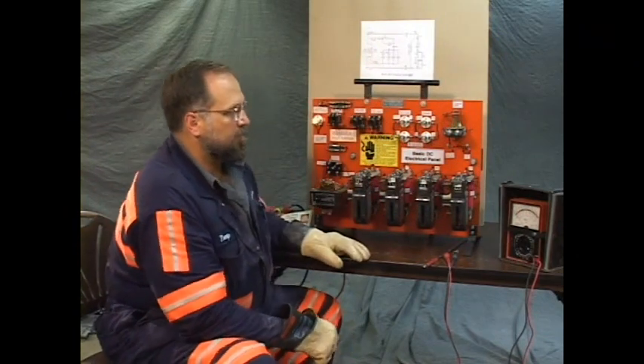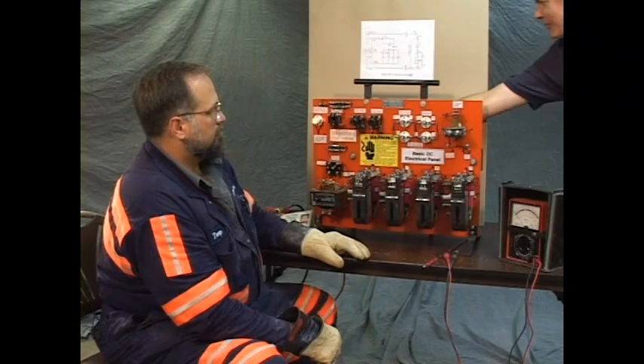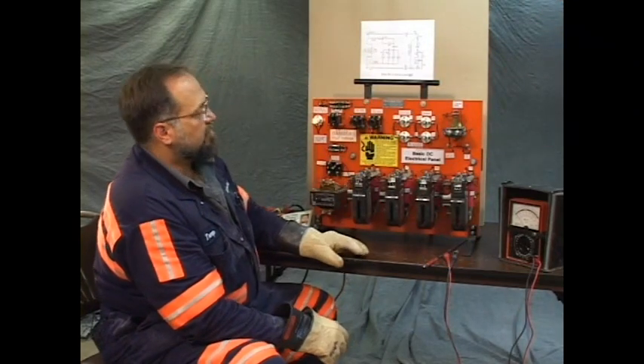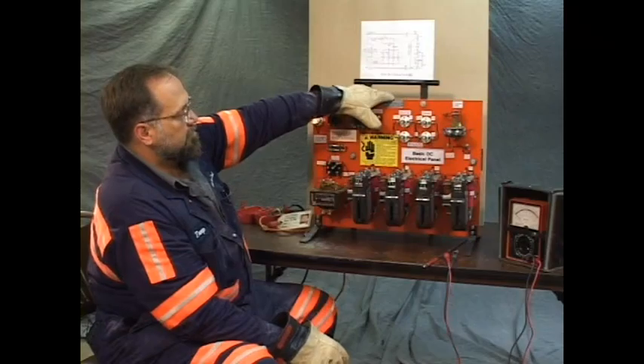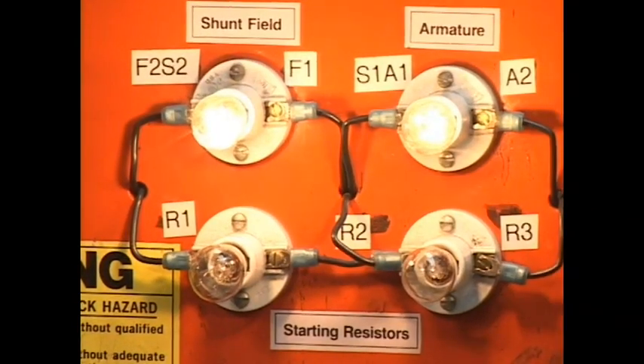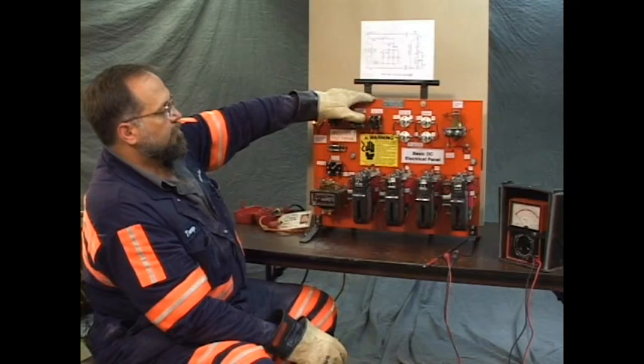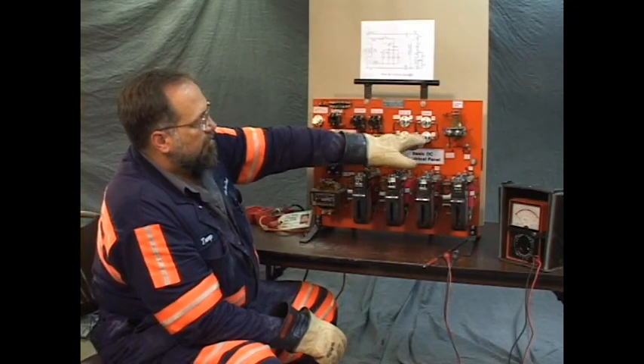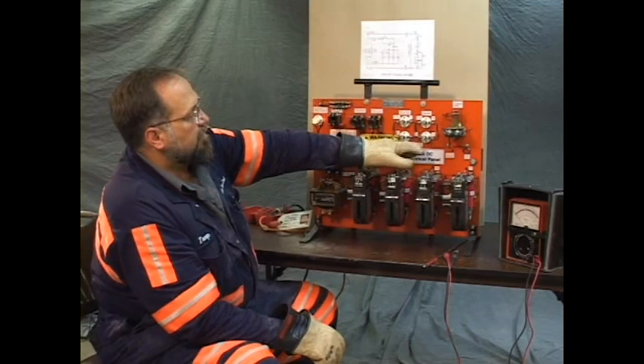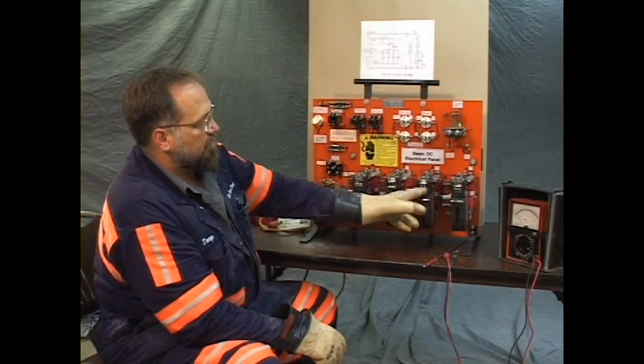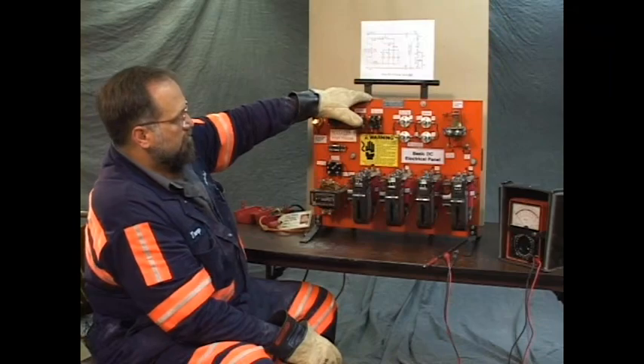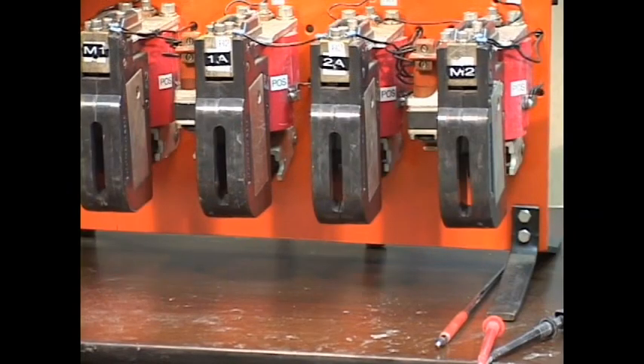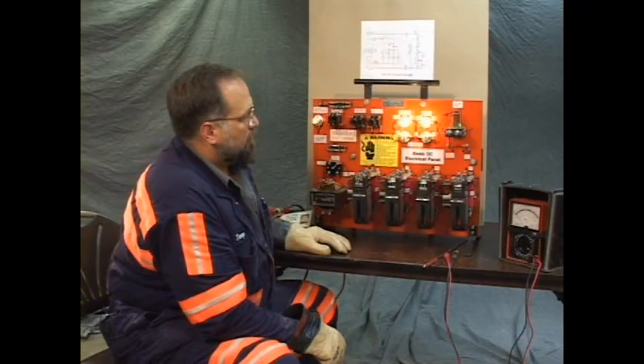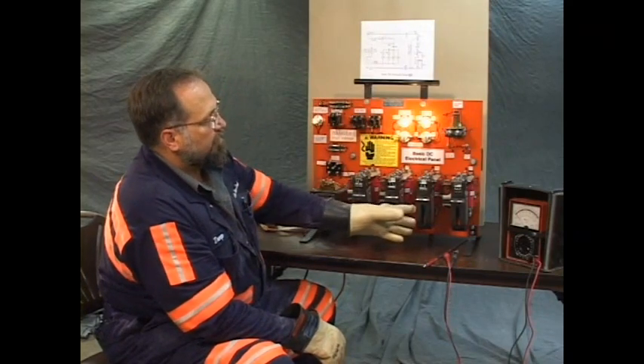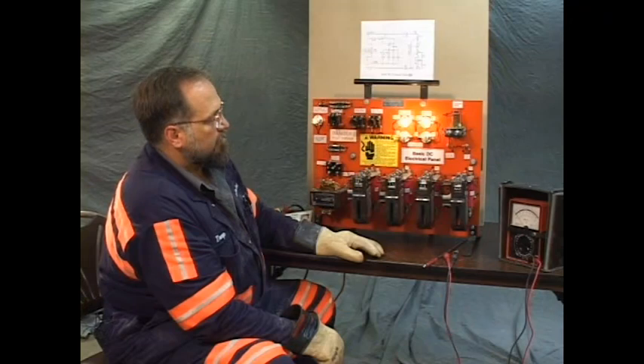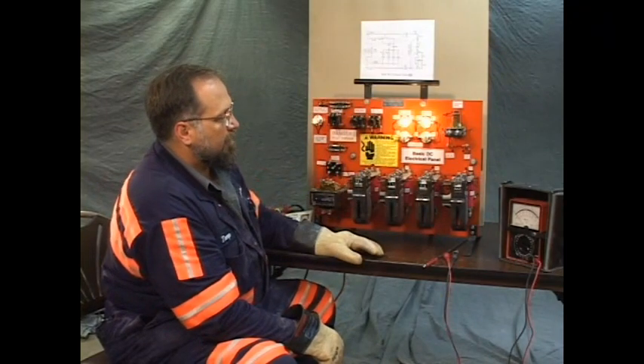Now, let's toggle the switch number 14. And with the problem installed, let's see what happens. I only heard 2 clicks. This light never came on at all. That part of the resistance symbolized by this light is controlled by this contact. Two clicks. The circuit has been abbreviated in that this contactor closed out of time.